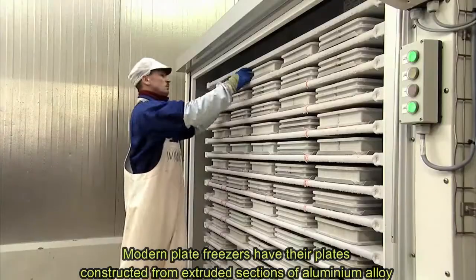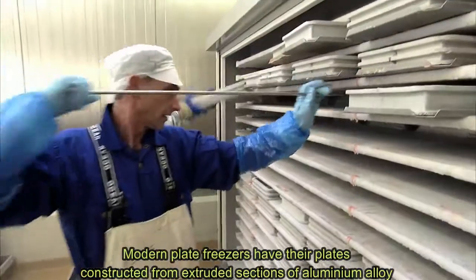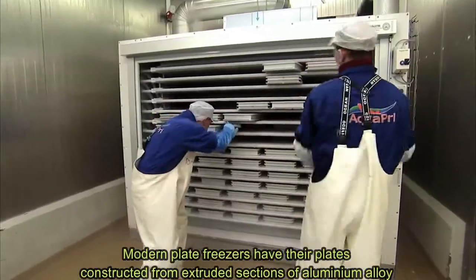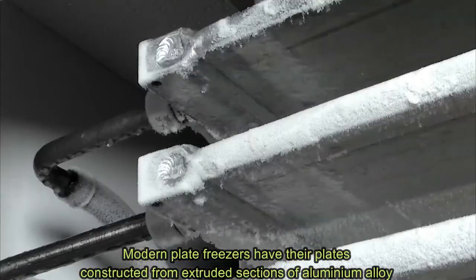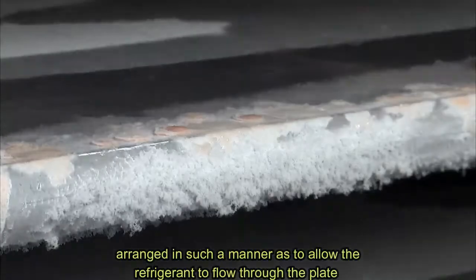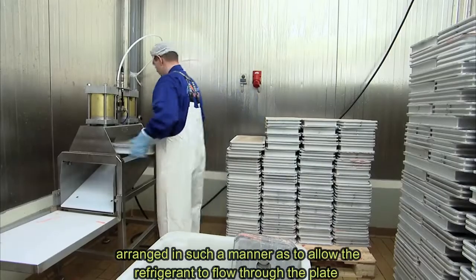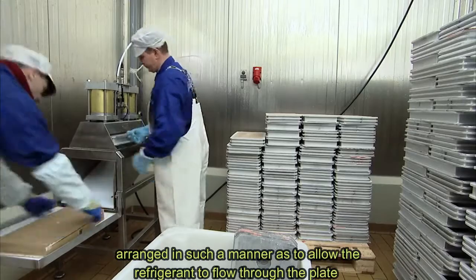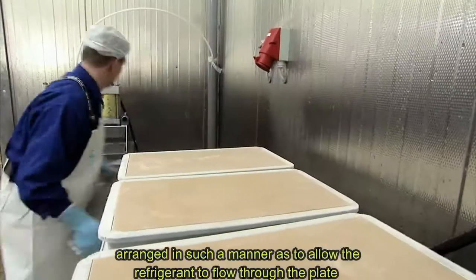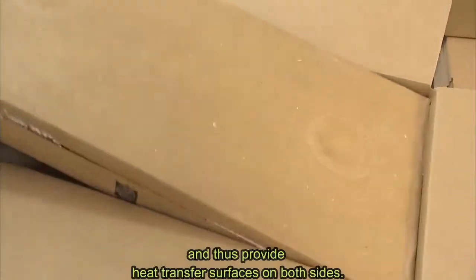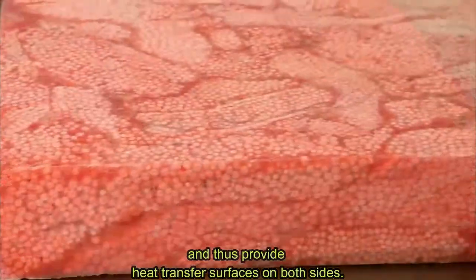Modern plate freezers have their plates constructed from extruded sections of aluminum alloy arranged in such a manner as to allow the refrigerant to flow through the plate and thus provide heat transfer surfaces on both sides.